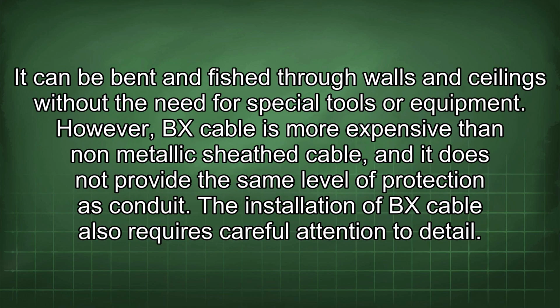It can be bent and fished through walls and ceilings without the need for special tools or equipment. However, BX cable is more expensive than non-metallic sheathed cable, and it does not provide the same level of protection as conduit. The installation of BX cable also requires careful attention to detail.